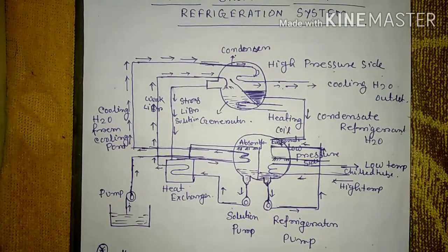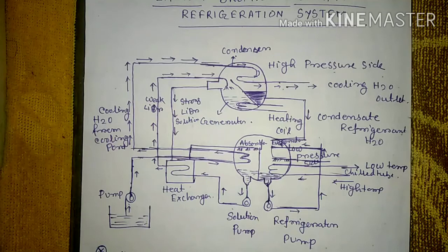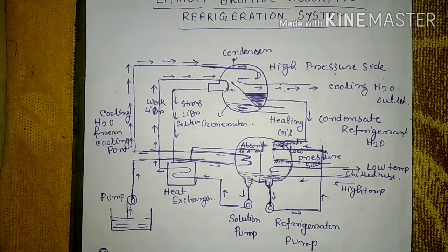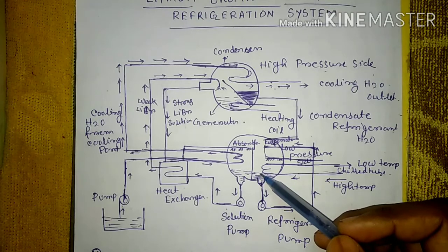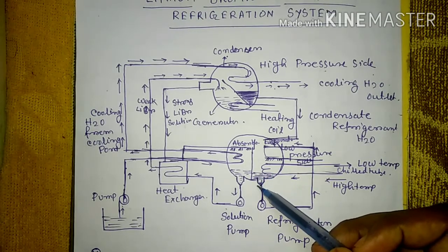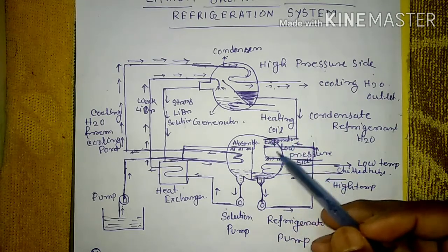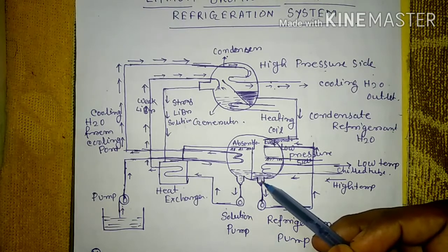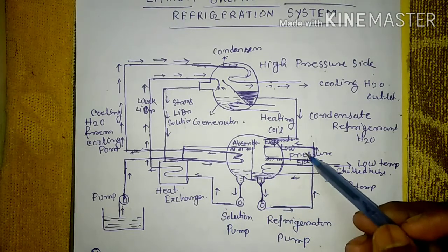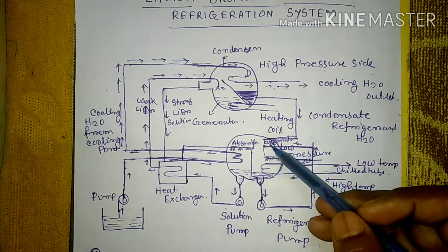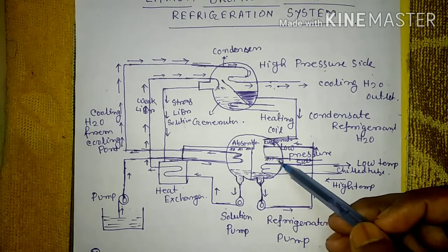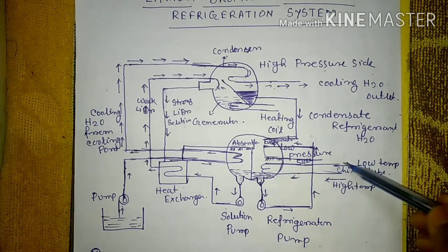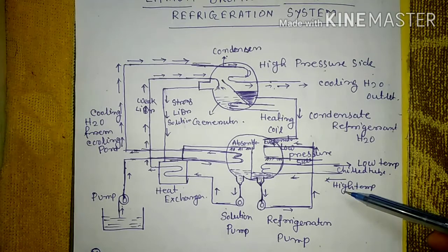Now, the working principle: water acts as the refrigerant in the evaporator. The water refrigerant is pumped via a refrigerant pump to a spray header, where it is sprayed through spray nozzles onto the chilled water tube. High-temperature water enters the chilled water tube and exits as low-temperature chilled water.